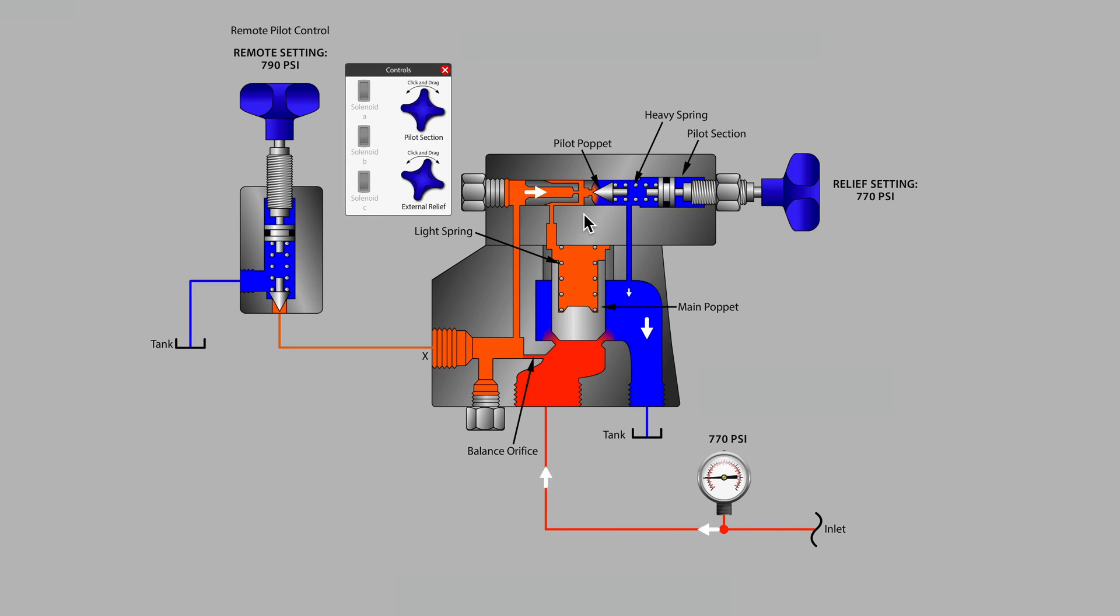You'd be quite correct to say that they are in parallel. One pilot section has flow back to tank here, and the other pilot section, if it is open, has flow back to tank there. So they are plumbed in parallel, and this is simply the case of path of least resistance where the pilot section that is set the lowest is in control of the main poppet for a pilot operated relief valve.